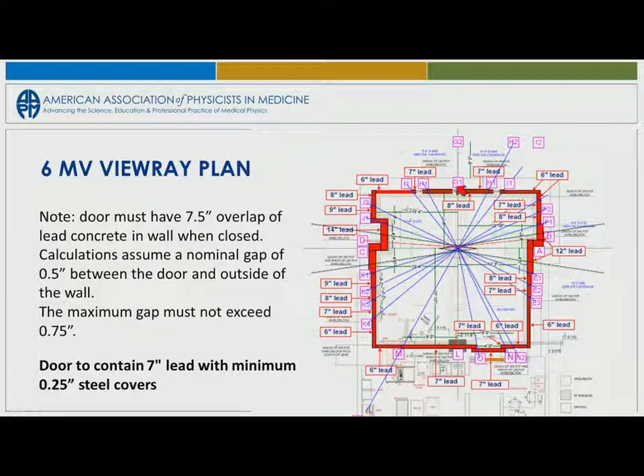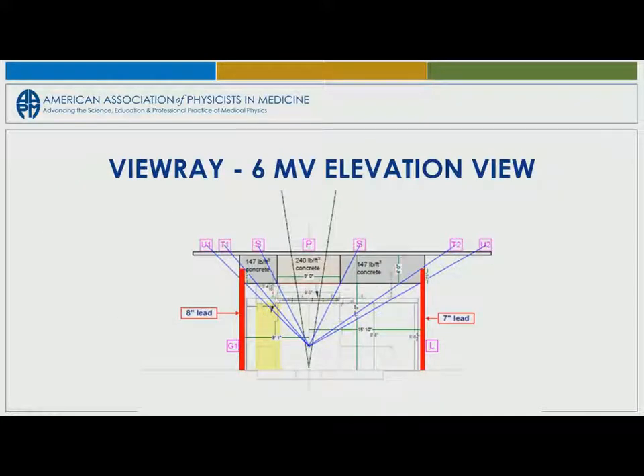You can do it all with lead brick. And again, it's a fairly small room. So if you're really challenged, you may be looking at some of these newer units to be able to fit them into a small room. You want flat surfaces, because realize they've got to get the MRI shielding. Your RF shielding has to go inside your X-ray shielding. So you want flat walls. You don't want these bump out walls. You either want the bump out on the outside, or you want to do it with HD concrete or lead in your ceiling. But your RF shielding for your MRI unit has to be inside all of your X-ray shielding.